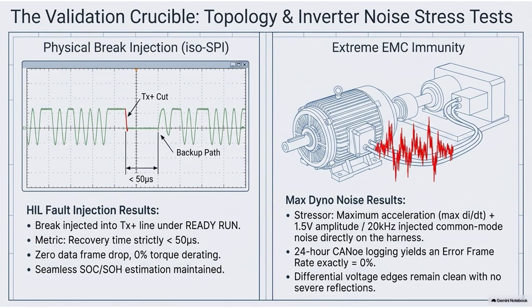Okay, let's do the math on this because it's a beautiful proof. We have a long wire. We have a 120 ohm resistor soldered at the far left end. We have a second 120 ohm resistor soldered at the far right end. And basic electrical physics dictates that when you have two resistors of equal value wired across the same two lines, wired in parallel, the total resistance of the entire circuit is exactly half the value of one resistor. So 120 divided by 2 is 60. Therefore, the test machine must read exactly 60 ohms. The factory specification demands the reading must fall exactly between 59 and 61 ohms.